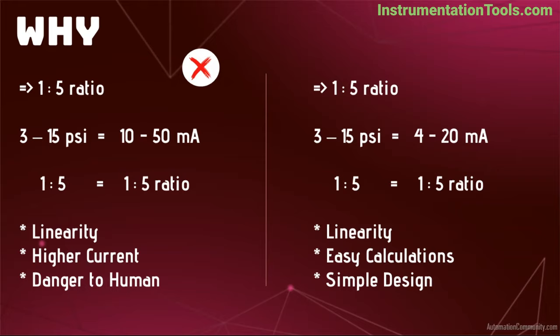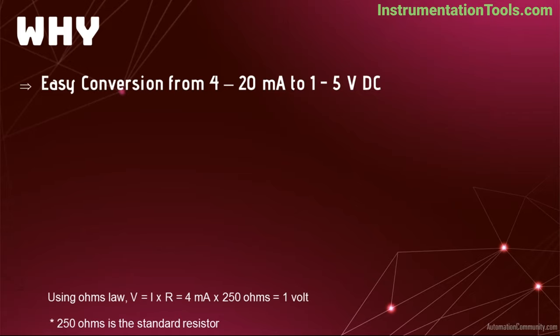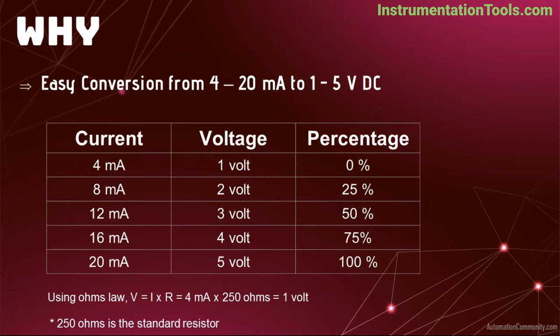One of the main advantages of using 4 to 20 mA signals is that it simplifies signal conversion from current to voltage. A simple 250 ohm precision resistor is sufficient to convert 4 to 20 mA signals into the equivalent 1 to 5 volts. Using the formula voltage equals current multiplied by resistance: 4 mA times 250 ohms equals 1 volt, and 20 mA times 250 ohms equals 5 volts. This makes calculations and conversions easy.